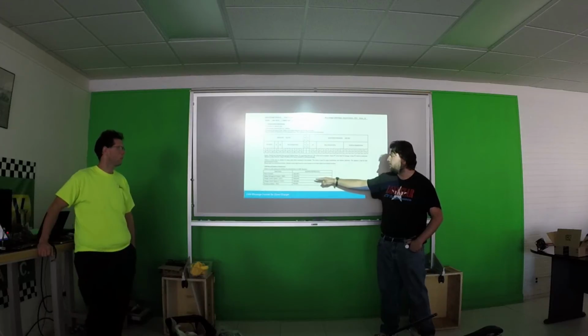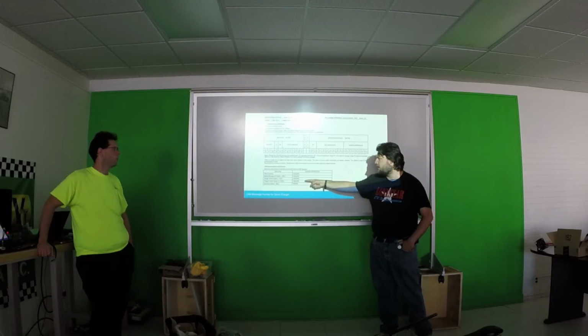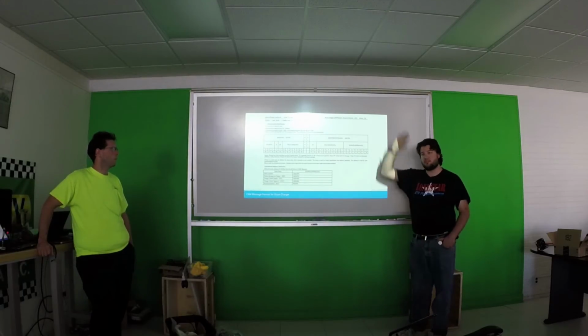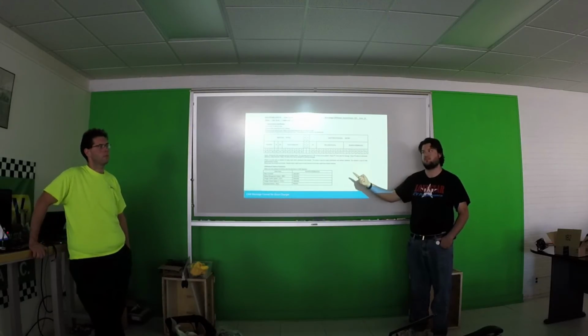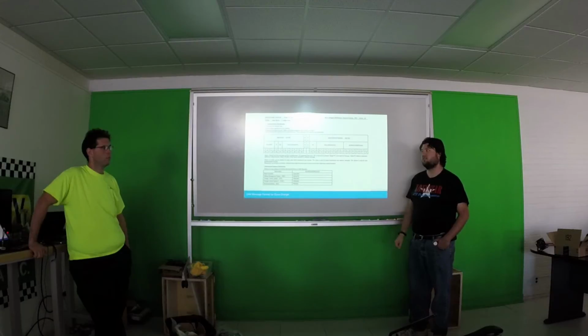When we're talking to the EVCON, this actually came from the EVCON spec sheet. EVCON is expecting messages from an F4. Actually, it doesn't care what the source address is for the BMS. It tells you what it wants it to be. No, it broadcasts; it tells you what it is. It will be sending out broadcast messages of here is the current voltage and current and my status bits, and then you have to send a destination specific message to it. I believe it doesn't care what your source address is, but you have to have the destination address correct, otherwise it doesn't listen.